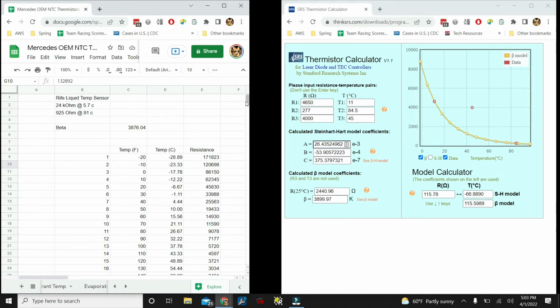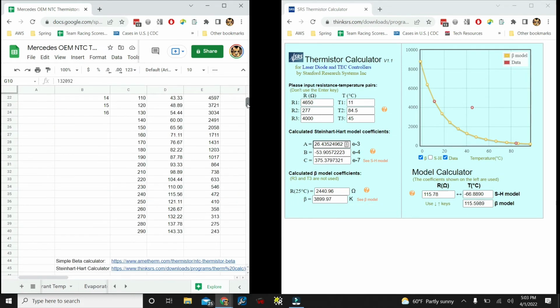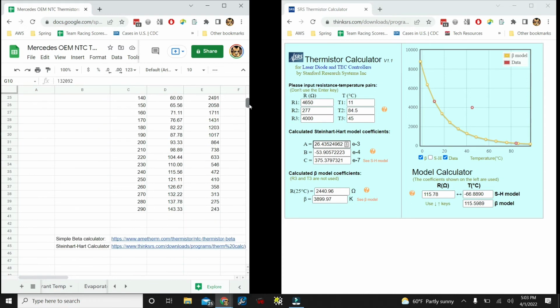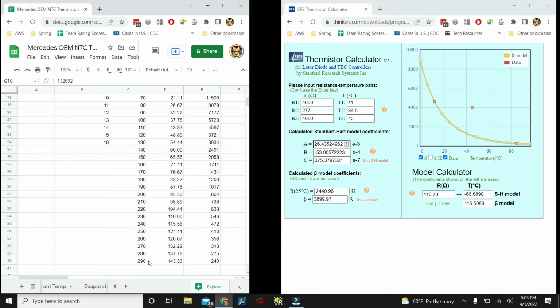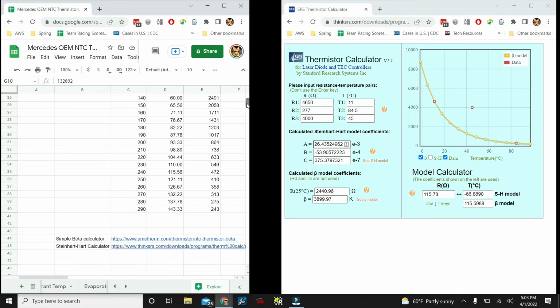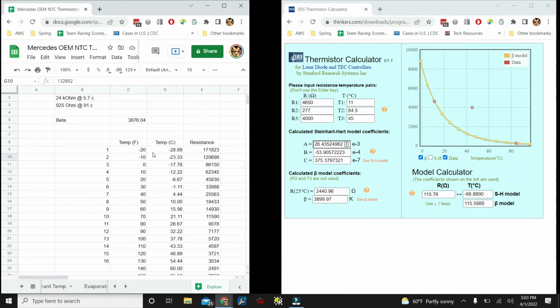So I set up a table just like I did for the other sensor, except this time instead of 16 values I went to 32, or however many it is, because that's what their calibration sheet has. It starts at -20 Fahrenheit and goes to 290. I wanted to try and back into the same values they had, so I used the same starting point. And again, I converted it to Celsius because I put each of these values into this calculator, and it came up with my resistance value.